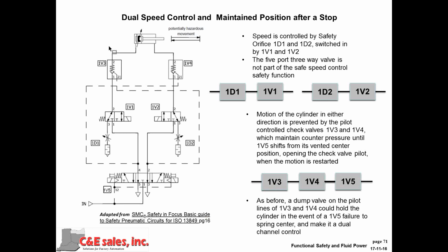If I want to discuss them individually, then the reliability would be a little bit higher because I have only two devices in there instead of three. The argument, of course, would be, well, yes, but is there really any difference between the motion of the two? There might be an issue where the hazard is higher in one direction than the other, and I don't want to include the check valve in the one area in that discussion.